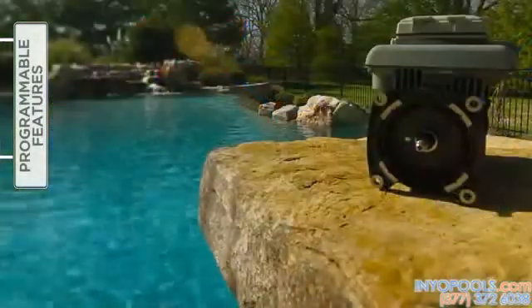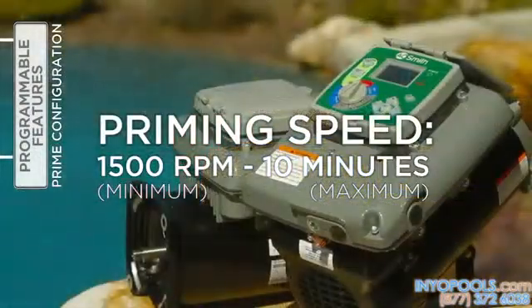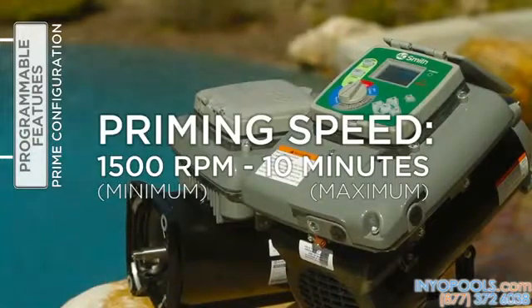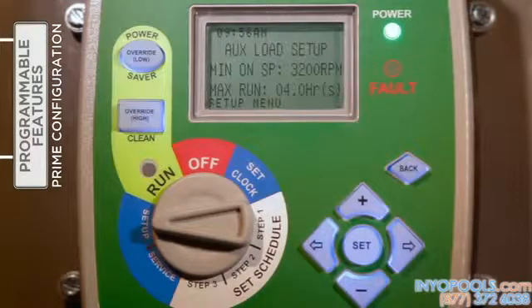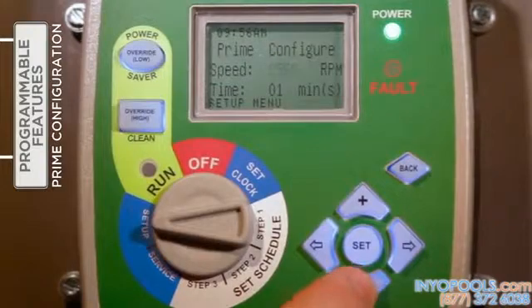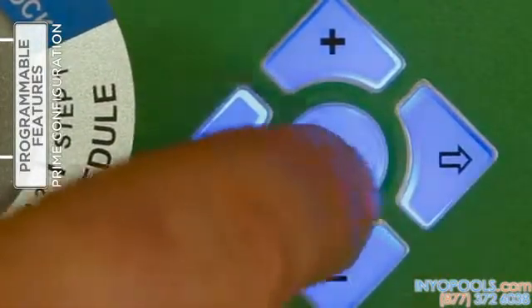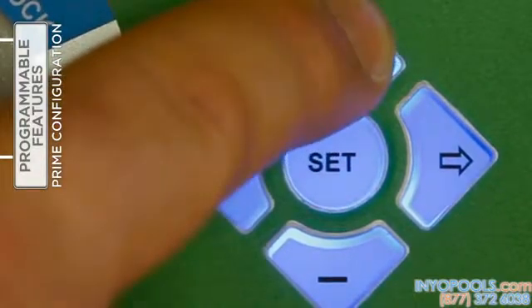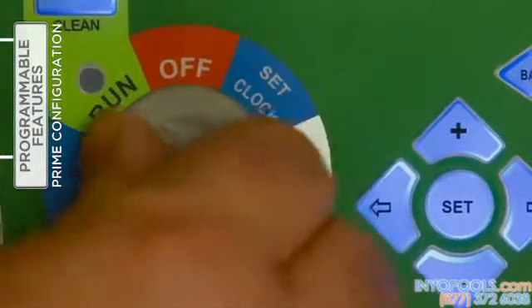The priming speed and duration can be adjusted under 'Setup.' Be aware that the minimum priming speed is 1,500 RPM and the maximum priming time is 10 minutes. With the selector switch turned to 'Setup,' use the right arrow button to access the prime configuration feature. Press 'Set' to enter change mode, then use the plus or minus buttons to increase or decrease the prime speed. Press the right arrow to move to the prime time field and use plus or minus to increase or decrease the duration.